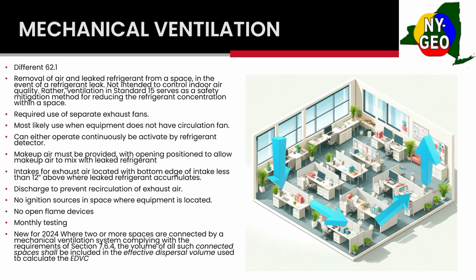For the fans used for this, you need to have separate exhaust and supply fans. You need to do two completely separate systems. Fans need to be UL 507 or UL 705 listed. They can either operate continuously or be activated by the alarm. The makeup air must be positioned to allow it to mix with the refrigerant, so it's got to be lower to the ground. It can't be like a high exhaust. Again, same with the intakes and the exhaust, no higher than 12 inches above the floor.